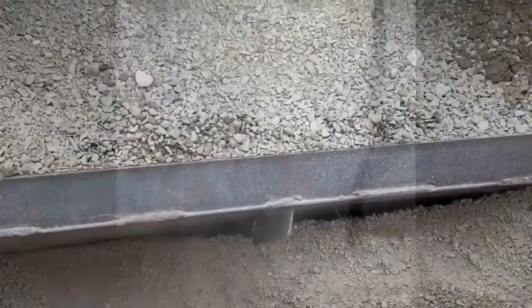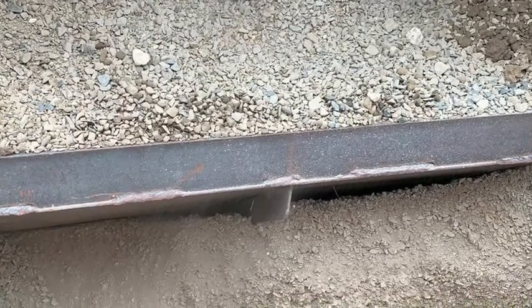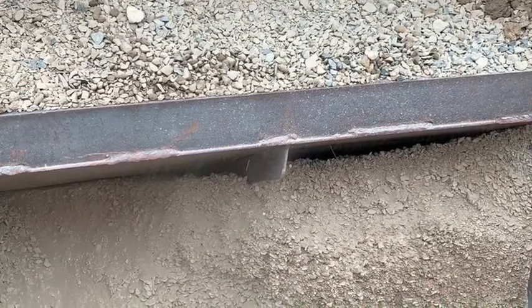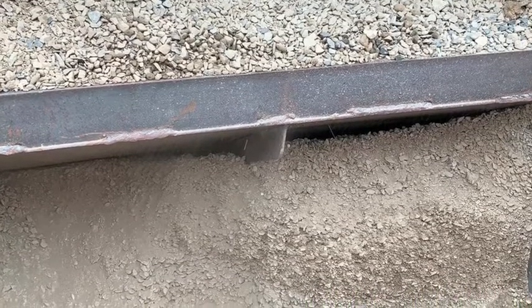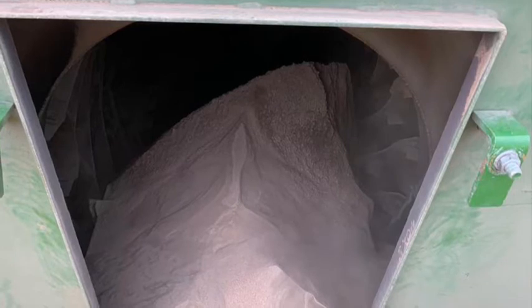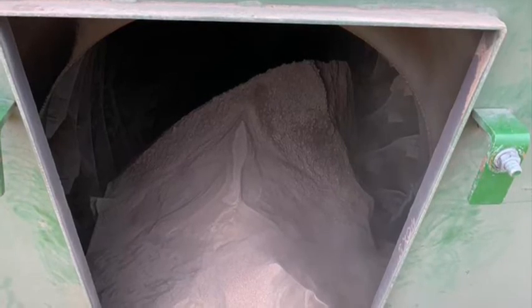With the back end of your dryer now blocked up, the dust extraction system will now concentrate on your inclined feed. That will now suck wet material into your skimmer baghouse, stopping your plant. In winter and periods of particularly wet weather, you really do need to keep an eye on your incoming aggregate sources, because if it's wet, you're just going to have the same problems that I've had with blocking dryers up. Get your loading shovel drivers to load a foot above the stockpiles to stop this.